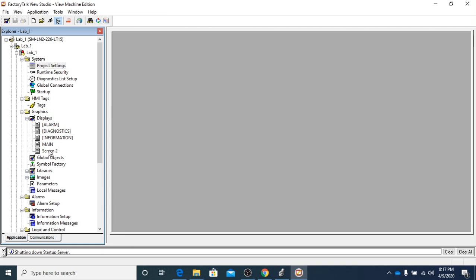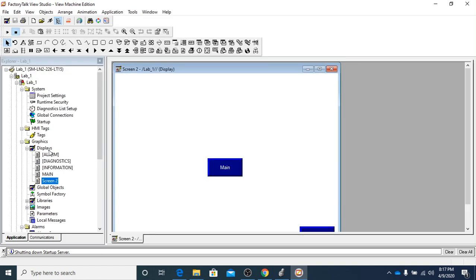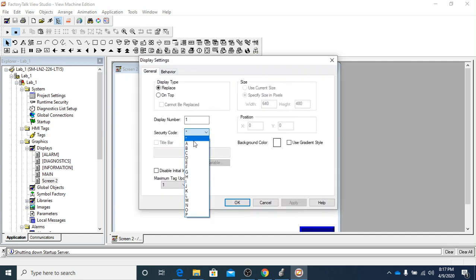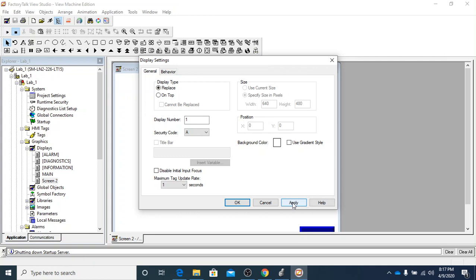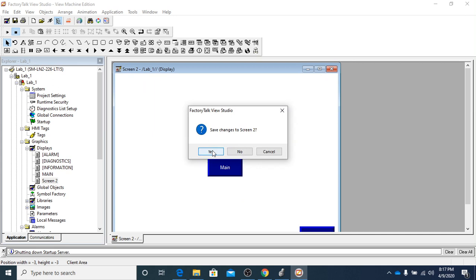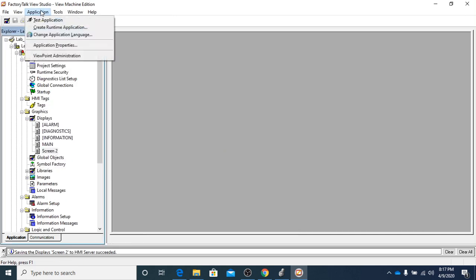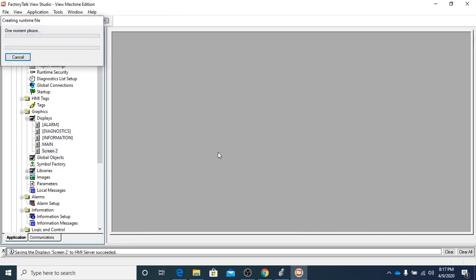What I did wrong was that screen two — if we open screen two back up, make sure it says screen two at the top — then you want to right click, go to display settings. We want to change the security code to A, because unless you are logged in as MAINT, screen two is not going to be available to you. So we've got to change that to A, go back through and X, save the changes, then go back up and do a test application.